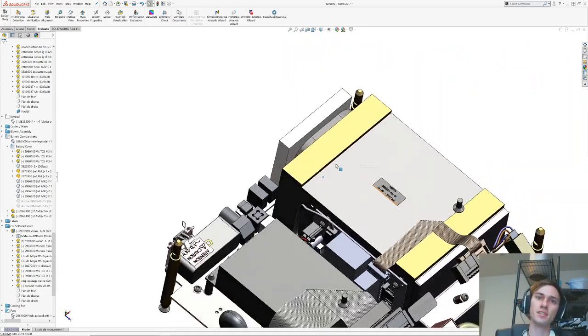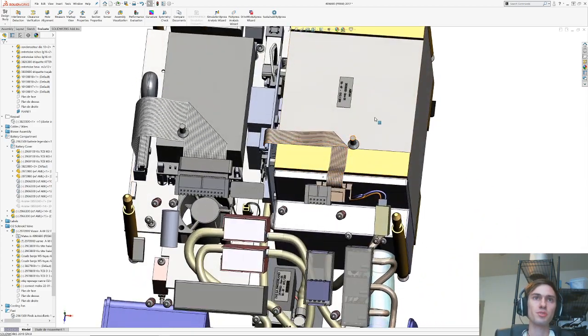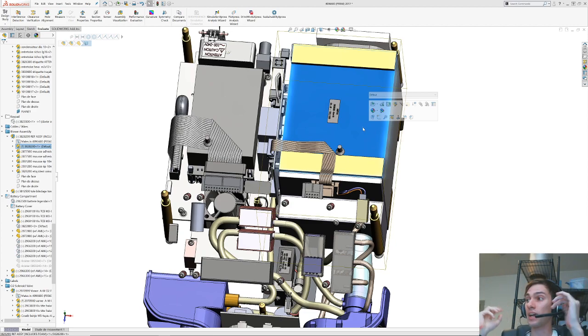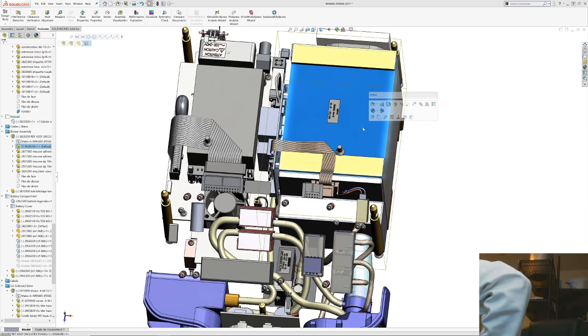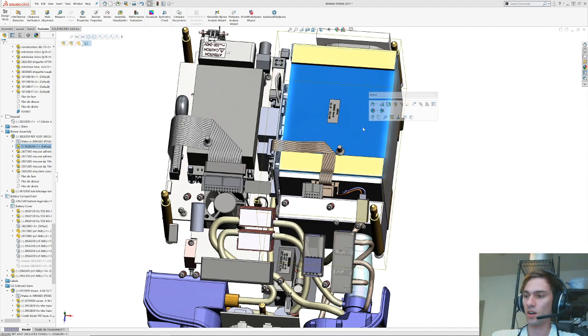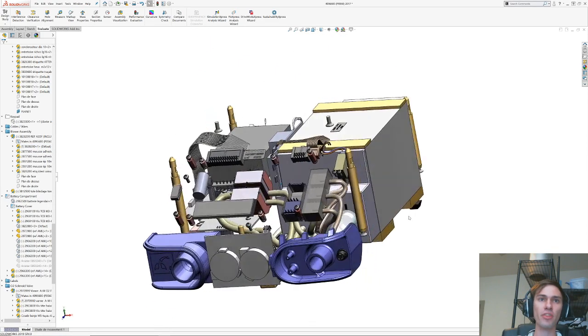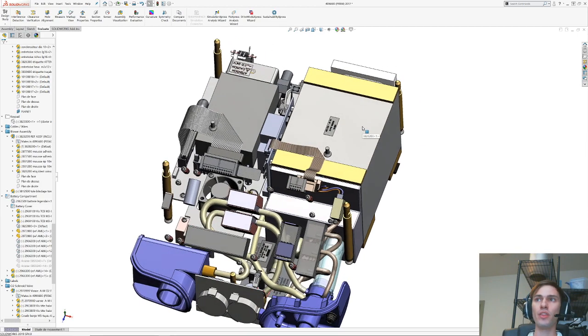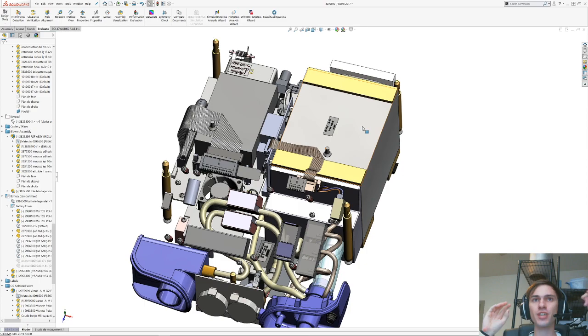Okay, cool. So this is something that 3D printed machines do not do often. Most of the 3D printed machines that I have seen are of the, let's see, the Nautilus gear style. This is one that I've been working on, where it's got a stepper motor that can control the position of a Nautilus gear to depress an ambu bag. And I think that's a really good way to do it with the limitations that amateurs have, but I think this is even better. Because if you can have valves, then you can just always be generating the pressure you need and then just open and close a valve, and the valve timing determines the tidal volume of air.